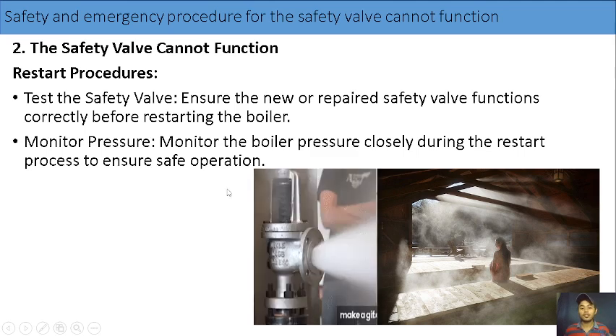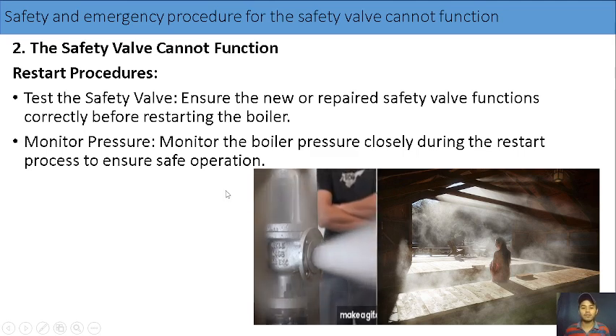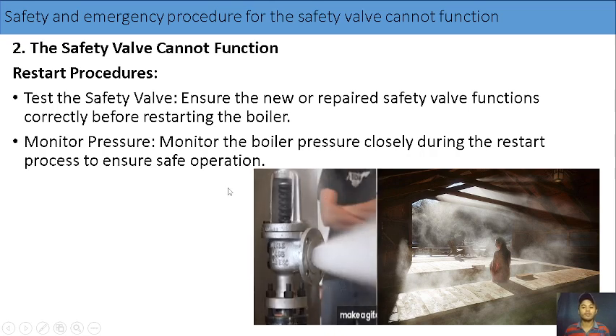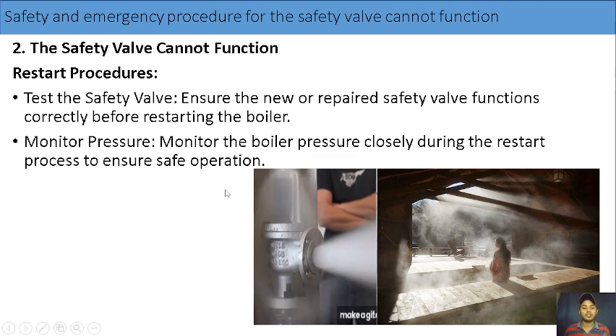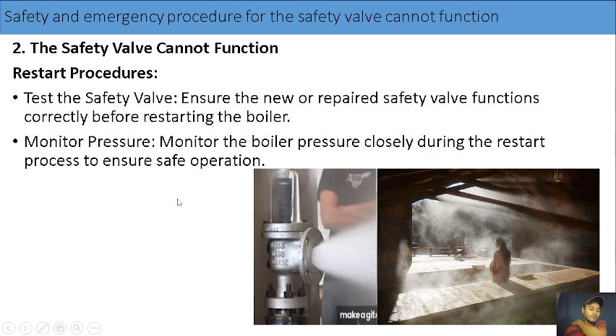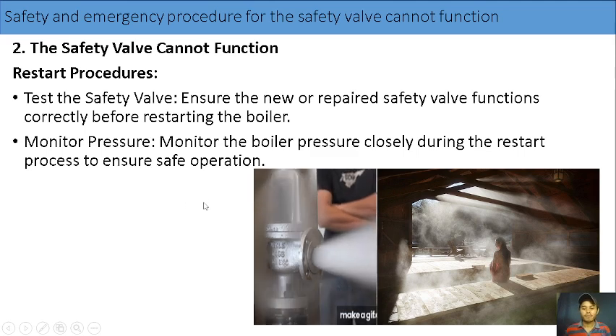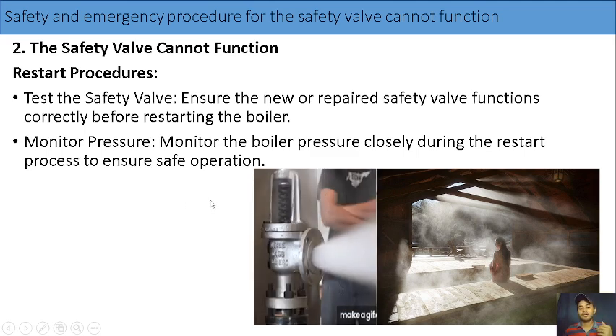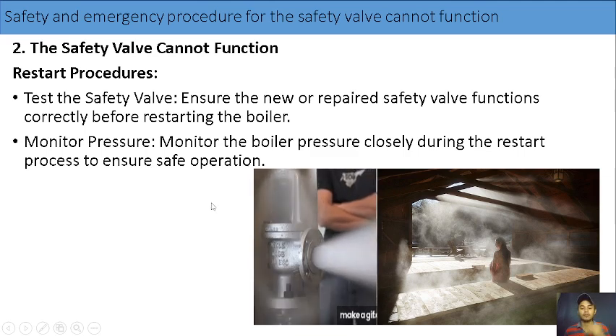Test the safety valve. Ensure the new or repaired safety valve functions correctly before starting the boiler. Then, monitor the boiler pressure closely during the restart process to ensure safe operation. And try to activate the safety valve at the right setting. For example, if it activates at around 8.5 bar, be sure that at 8.5 bar it will open. There is a sight glass. You can see if there is flow at the safety valve outlet, and then adjust if the steam pressure is not correct on the setting.